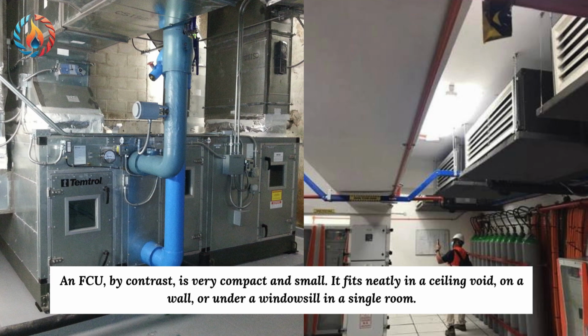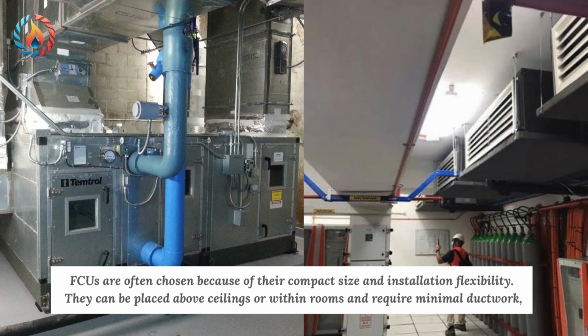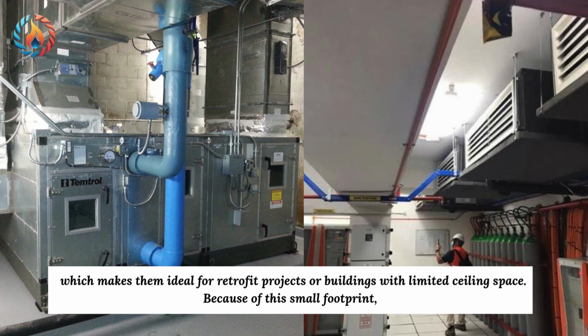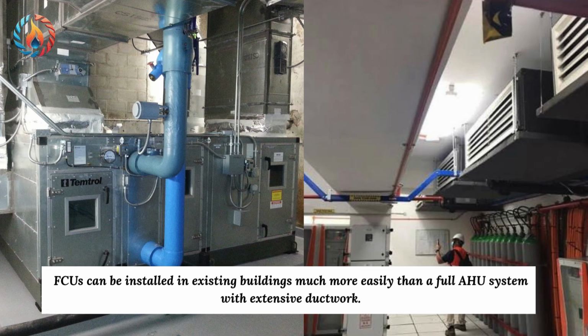An FCU, by contrast, is very compact and small. It fits neatly in a ceiling void, on a wall, or under a windowsill in a single room. FCUs are often chosen because of their compact size and installation flexibility. They can be placed above ceilings or within rooms and require minimal ductwork, which makes them ideal for retrofit projects or buildings with limited ceiling space. Because of this small footprint, FCUs can be installed in existing buildings much more easily than a full AHU system with extensive ductwork.